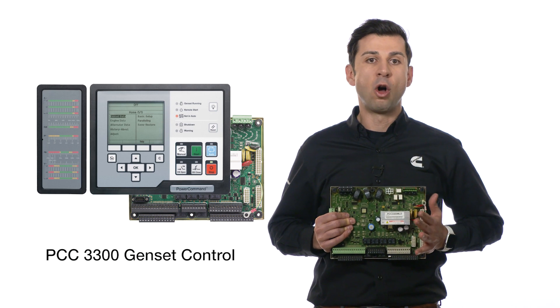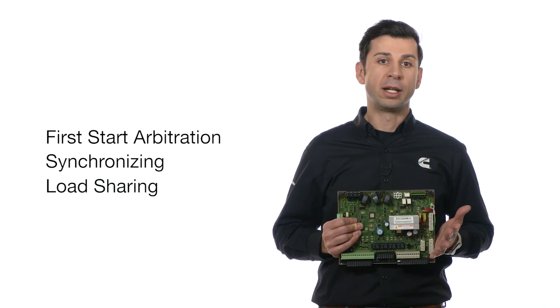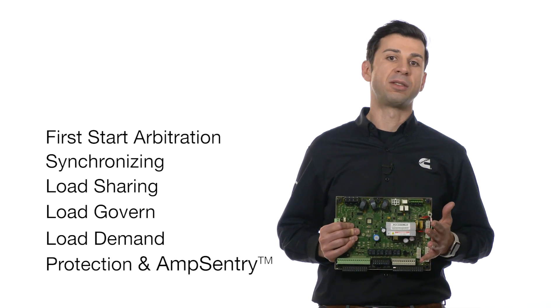It's responsible for all the paralleling functions, such as first-start arbitration, synchronizing, load sharing, load govern, load demand, and protection, which includes a UL-listed overcurrent function called AmpSentry.